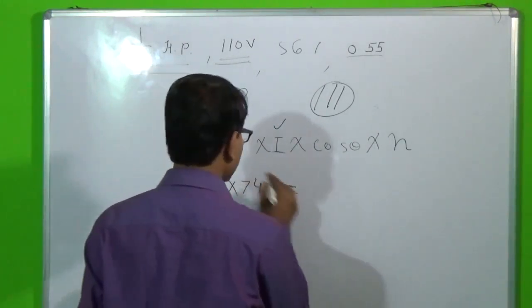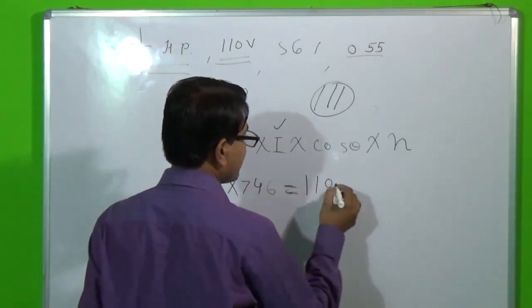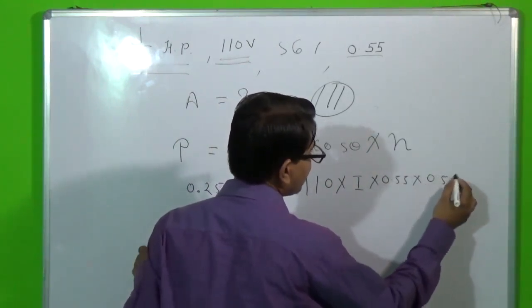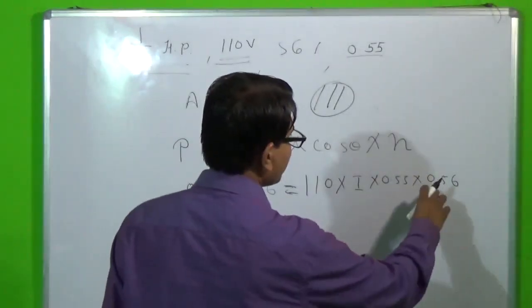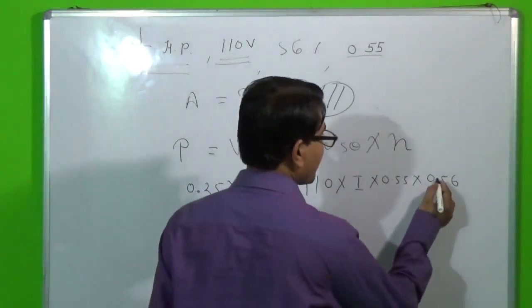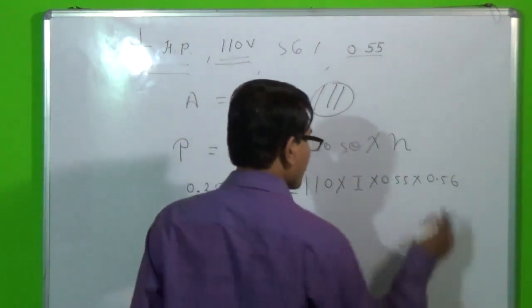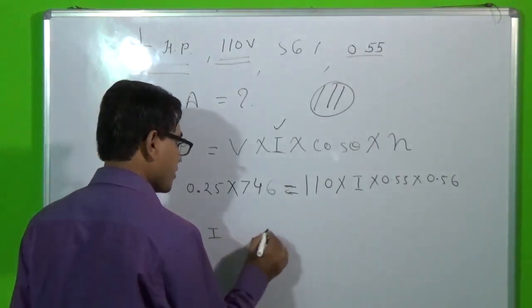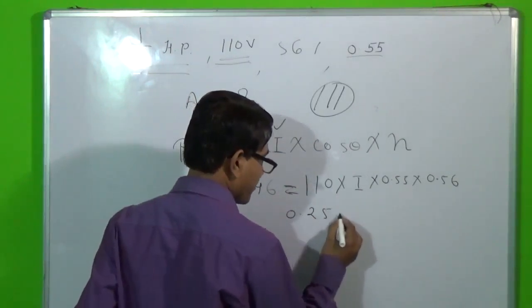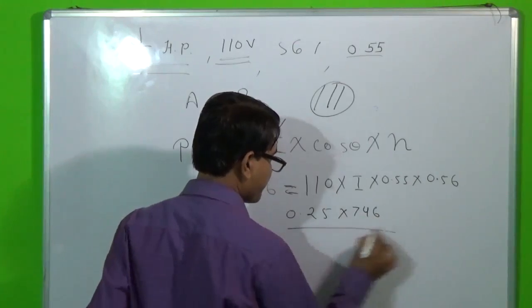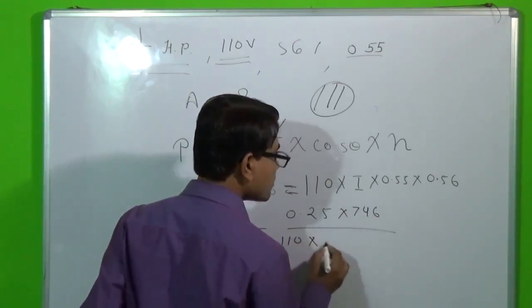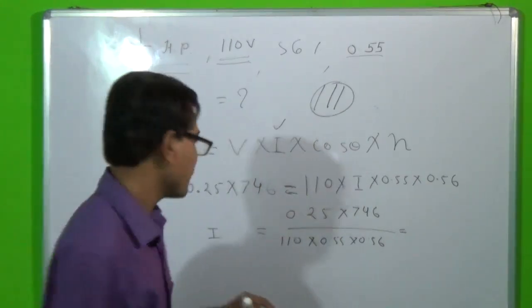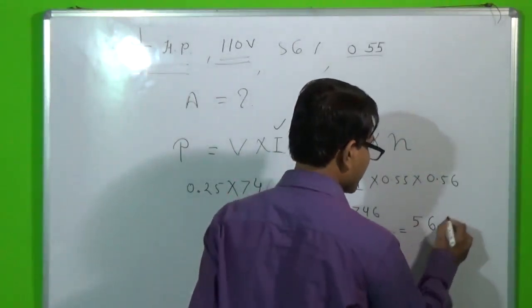V equals 110 volts, I is unknown, power factor is 0.55, and the machine is 56% efficient. Converting the percentage efficiency to a decimal, we divide by 100 to get 0.56. Solving for I, it becomes 0.25 × 746 divided by 110 × 0.55 × 0.56. Solving this equation, the current value comes out to 5.6 amperes.